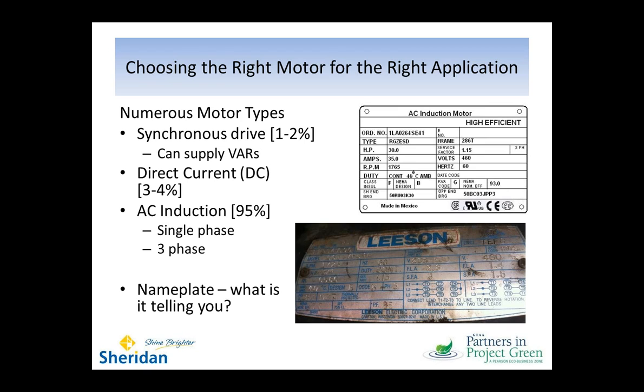I want to talk also about the various types of motors we see out in practice. In a fairly small percentage, we see synchronous motors, about 1 to 2% of the applications. The synchronous motor has a wound rotor, so the spinning part has windings on it. The stationary part has a number of poles, and its operating speed is tied to fractions of the frequency it sees.